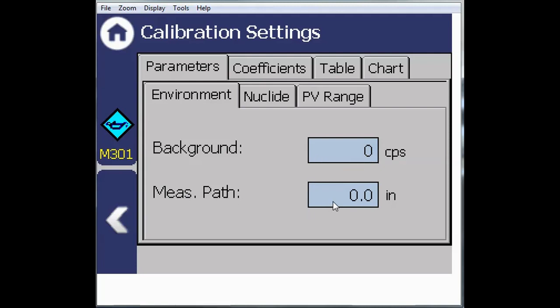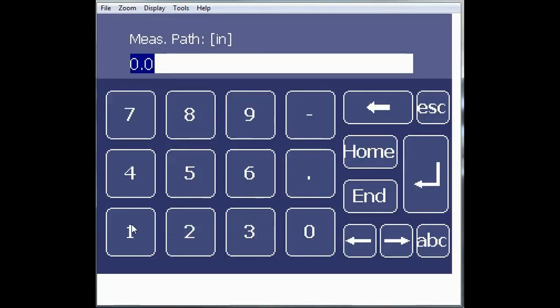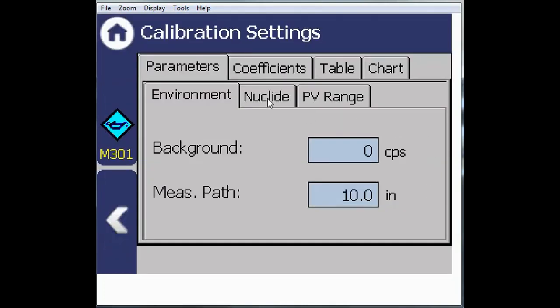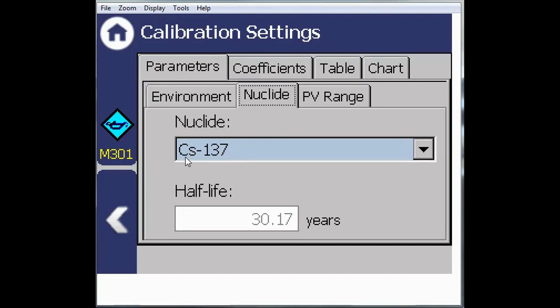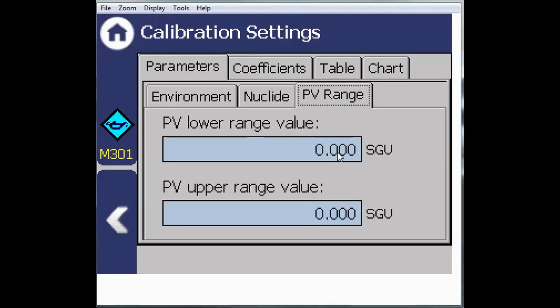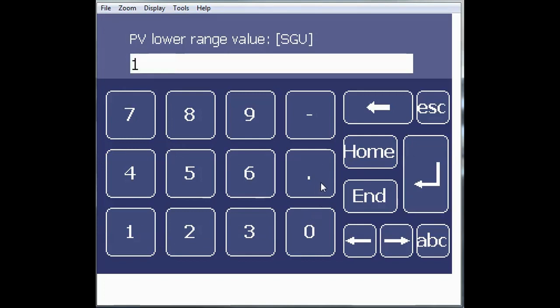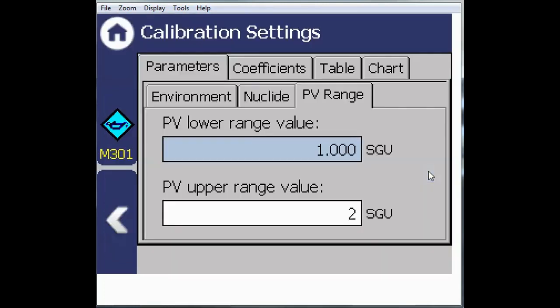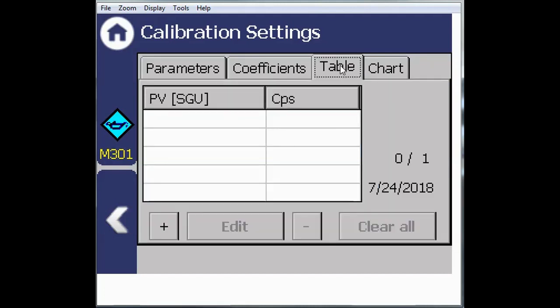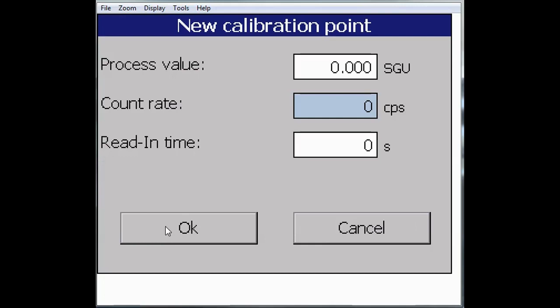The measuring path will be the inside diameter of the pipe that you're working with. So we'll click on this field and we're on 10-inch pipe. Ensure that your nuclide is the correct source for your application. The PV range. Now let's click on the Table tab. Notice that the table is empty. Select the plus to enter a new field.